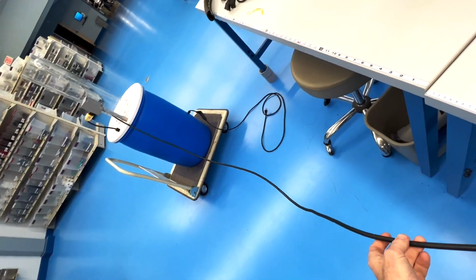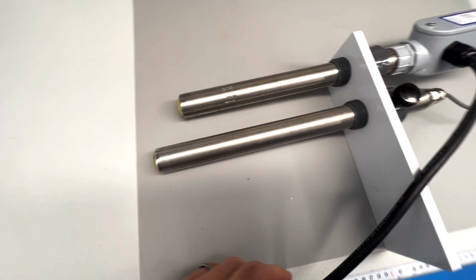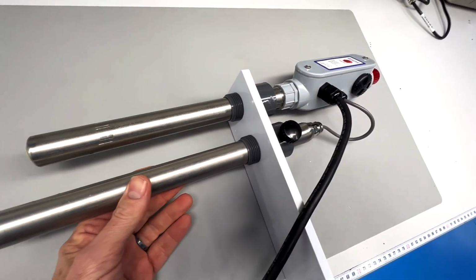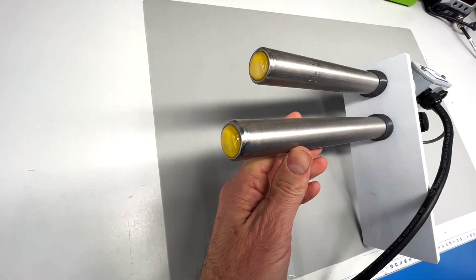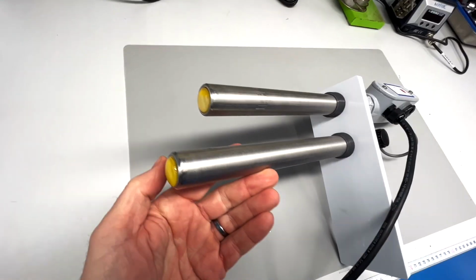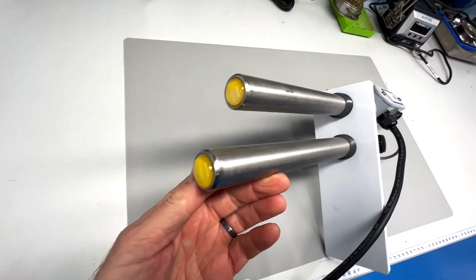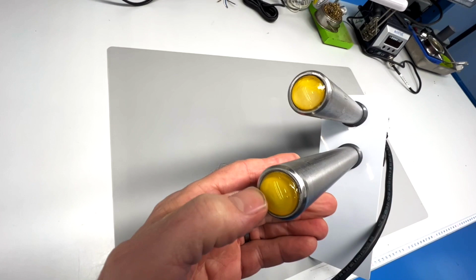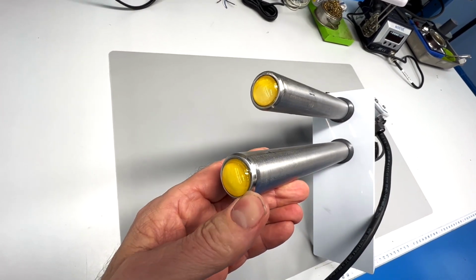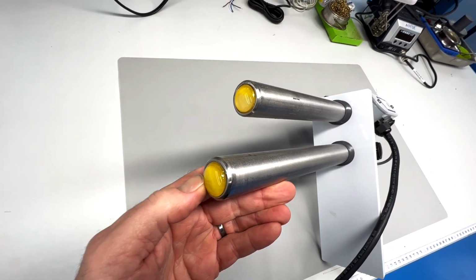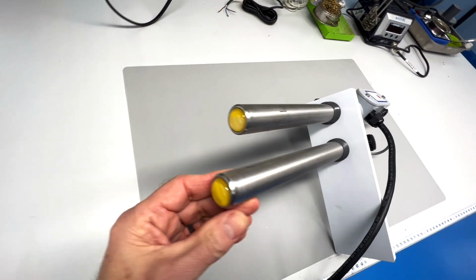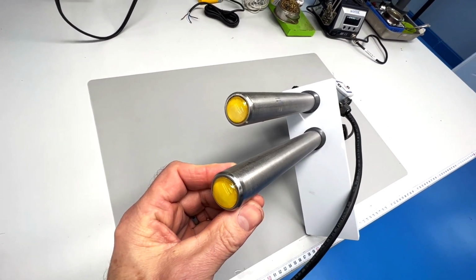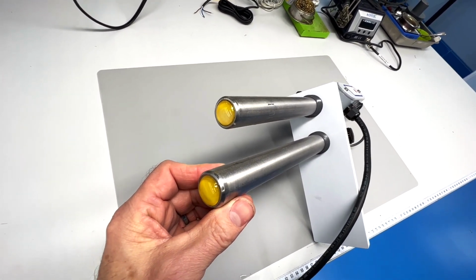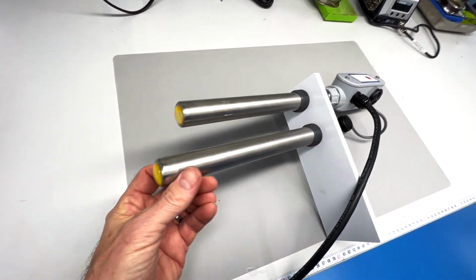We're going to put it in our test tank in a moment, but first I'll show you the details of the construction. Here we have stainless steel pipe, though normally plastic is more common - this is a special one. On the end there's a glass lens bonded with a very chemically resistant epoxy resin, typically used for sealing chemical reactors.